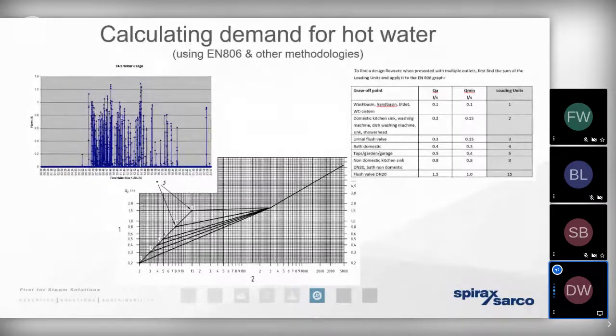So if we compare that with a plate heat exchanger that's generating hot water from steam instantly and on demand, we've completely eliminated that risk of oversizing. And it becomes slightly easier if we're looking at removing an old or an existing hot water storage calorifier and then replacing it with a plate heat exchanger, because all we need to do in circumstances such as this is fit a flow meter on the cold makeup. This is going to help us to understand how much hot water is required by the process. So I think perhaps the very, very worst thing we can do if we're looking at replacing a shell and tube heat exchanger with a plate heat exchanger is just replacing the duty like for like, because all we'd be doing is replicating that inefficiency.